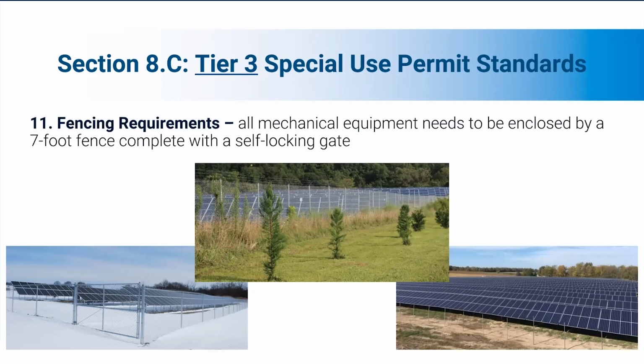Fencing: we require a 7-foot fence per the National Electric Code guidelines. I recommend checking the NEC because there's some wiggle room in fence type—for instance, you can allow a 6-foot fence if it has barbed wire on top. So there is some variation, but make sure the fencing complies with the National Electric Code.